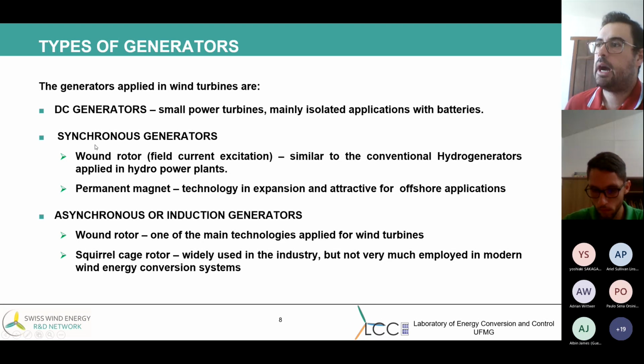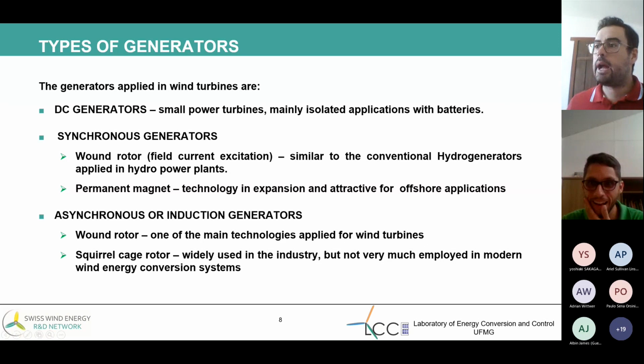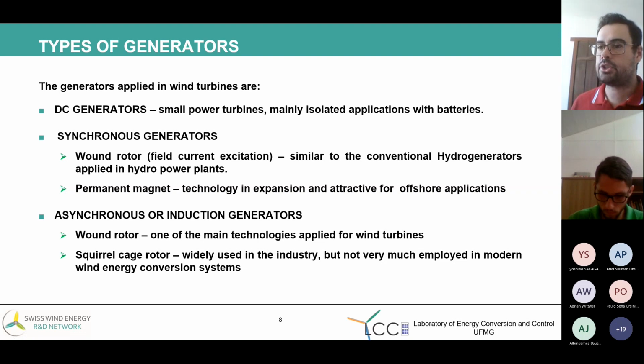The synchronous generators are divided in two types. One is wound rotor, or field current excitation, generators similar to the conventional hydro generators applied in hydro power plants. Of course, it's similar, it's not equal. When we have a hydro power plant, we have a generator generally with field current excitation, and then the generator is similar for the wind turbine application. We also have the permanent magnet synchronous generator. The technology is in expansion and very attractive for offshore applications.